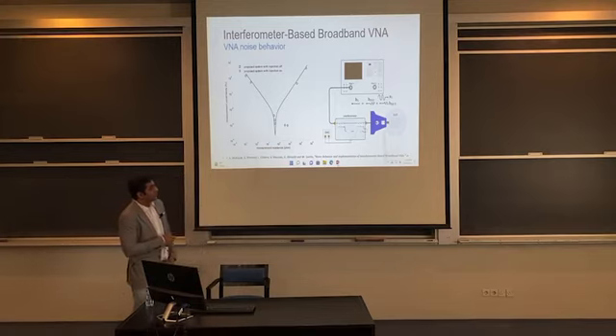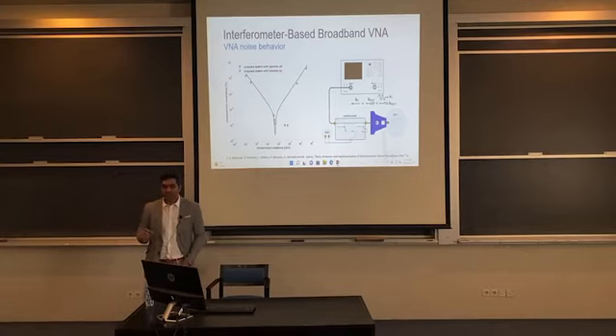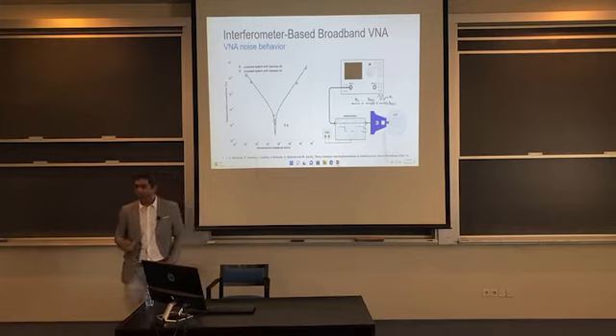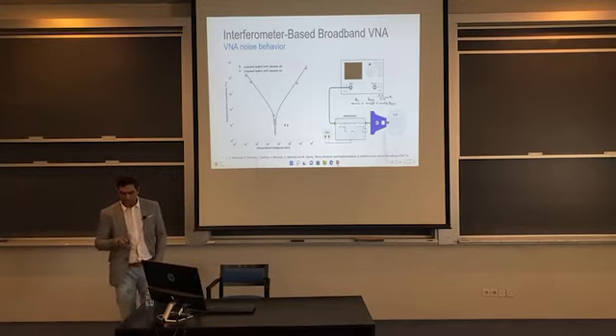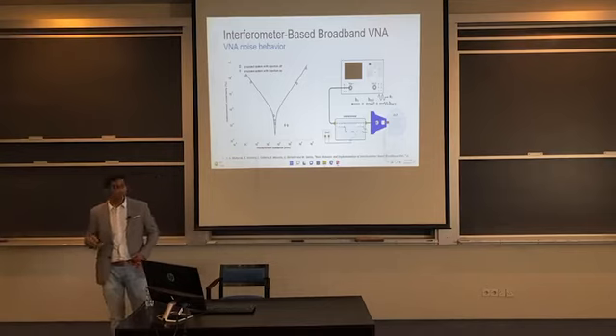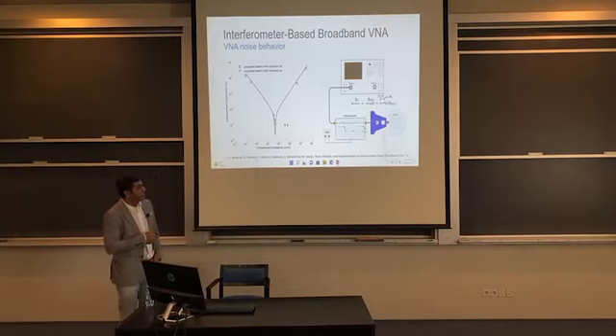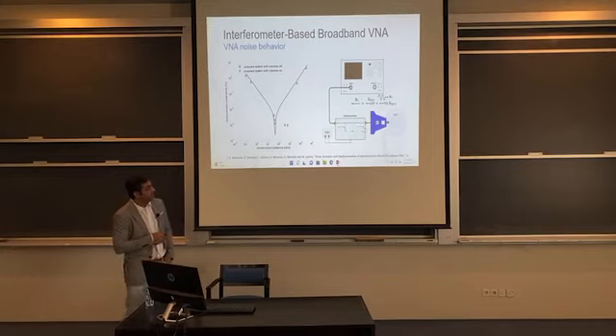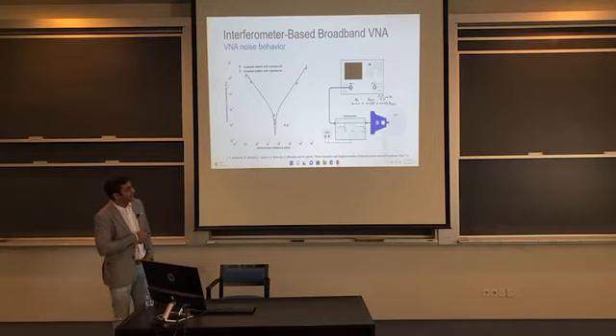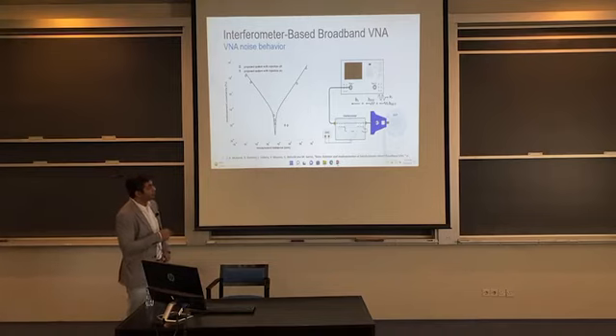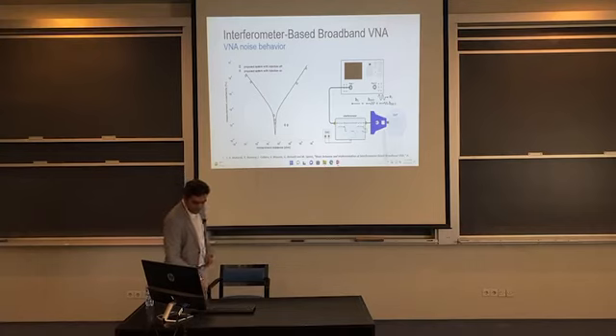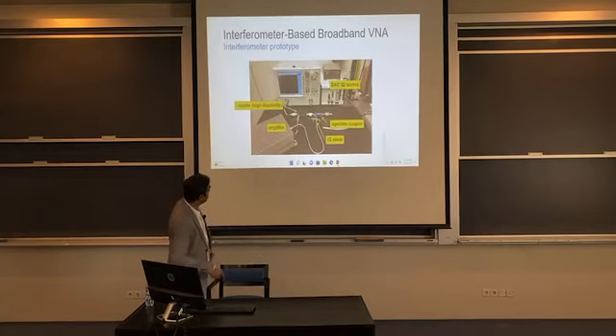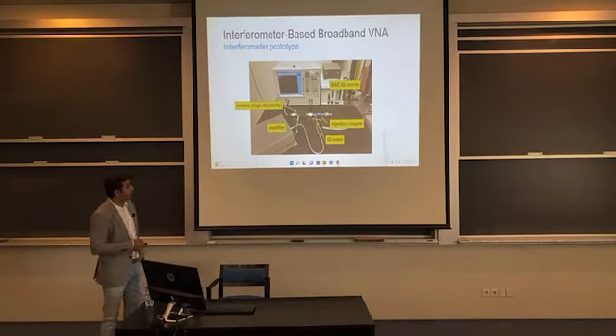Now, matched device means that your scattered wave is extremely small. Right? So if you have a matched 50 ohm load terminating the VNA, you have a very small reflected scattered wave. But in a mismatched loading condition, this scattered wave becomes very big. So what we do is we develop this interferometer which copies this incident wave and then basically cancels out this scattered wave, which is reflected by the DUT itself. We generate a second wave which cancels this one out. And the resulting B wave, which goes into the instrument, is extremely small. So the VNA thinks it's measuring a 50 ohm device while measuring these highly mismatched loads.